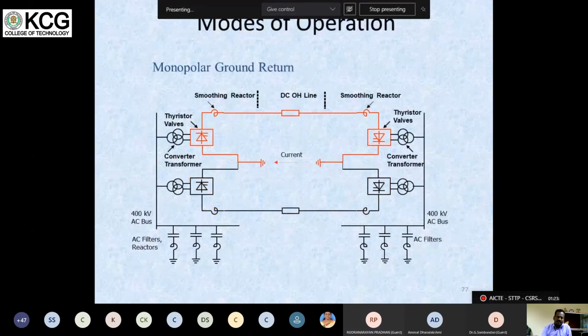The advantage of this system is that if any one line fails, or one transformer fails, or one converter inverter bank fails, with the available bank on the other side, 50% power can be transferred, which is not available in an AC system. In an AC system, if one phase is out, we have to shut down the total transmission line. But in a DC system, if one line, transformer or converter fails, we can transfer 50% power through ground return or metallic return also. If there is only a failure in the converter inverter station or transformer system, then 50% power can be transferred through the metallic return. Normally we don't use ground return, but we go for this 50% return in the DC system. This is an advantage of the HVDC system, which is very useful for grid operation. We can maintain the grid without much power loss.